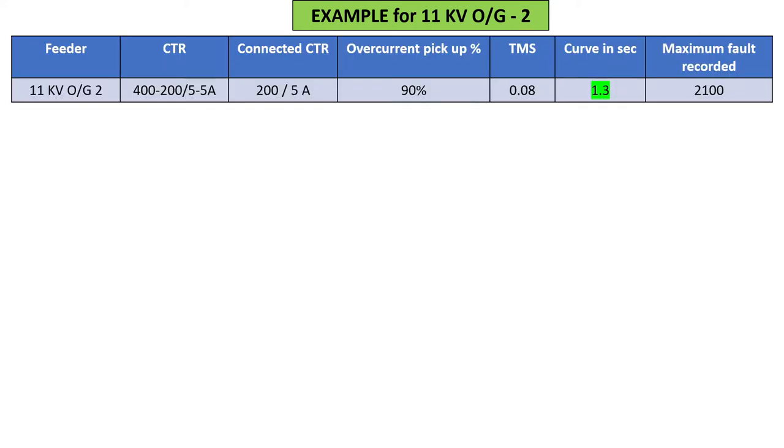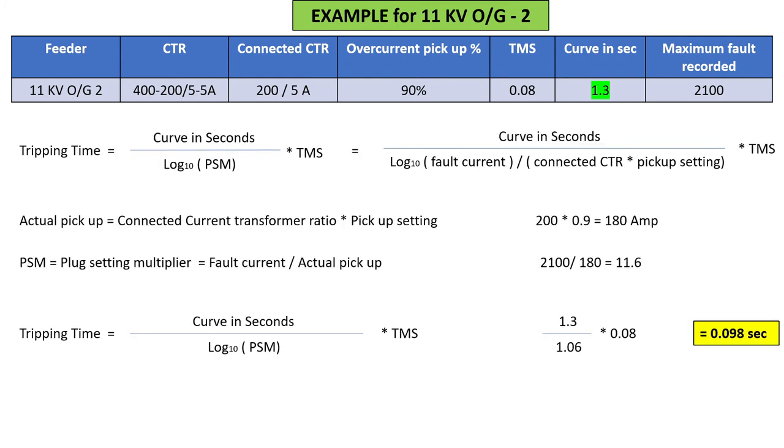Same for 11 kV outgoing feeder two. Here you can see the curve selector is different - you can select yours as per your site requirement. So tripping time here, using the same formula, comes out to be 0.098 seconds.